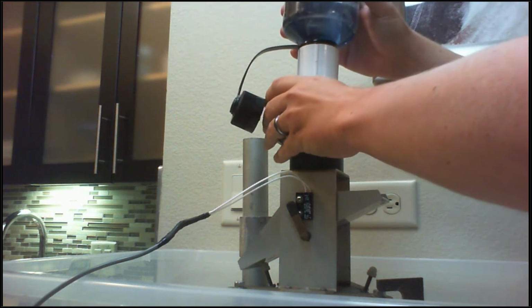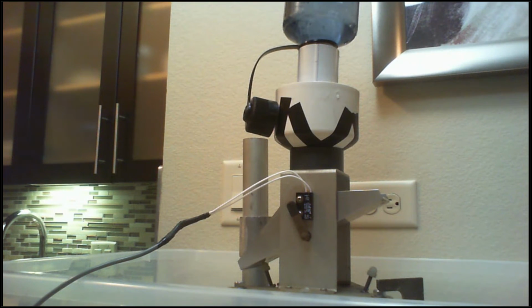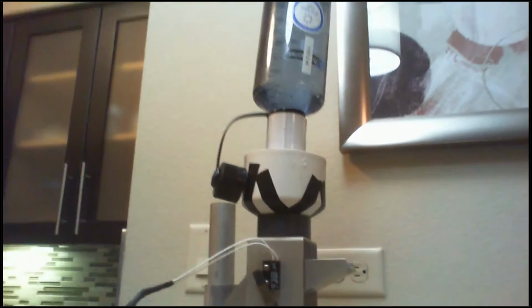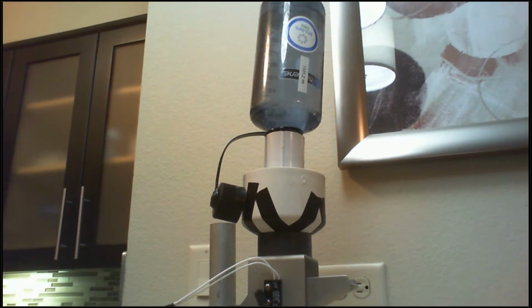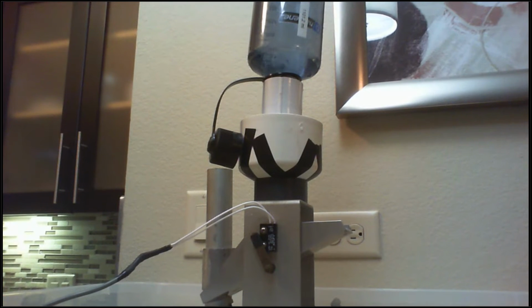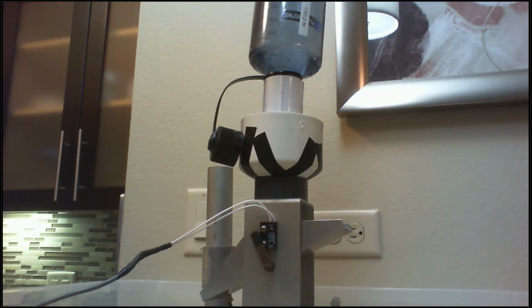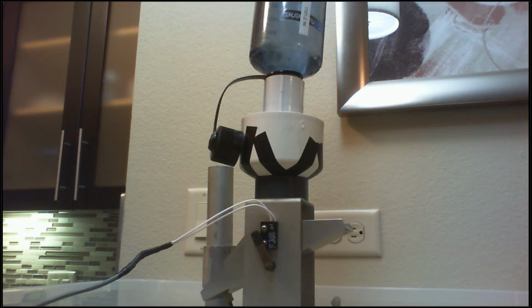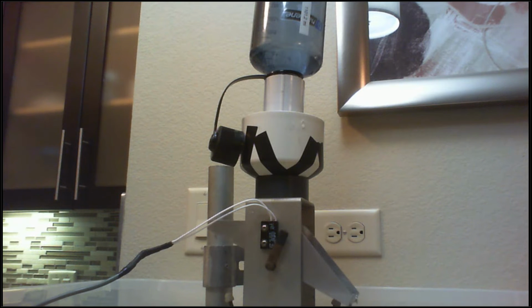And we want to make sure this is level and going straight into the funnel. So moving the camera just a little bit so you can see the full setup. We've got water coming through this calibrator into this tipping bucket. And we're really expecting to get 15 tips with just a little bit left over. We might get a little bit more, we might get a little bit less, but we'll see what we find. So first tip should be happening in just a moment. There it goes.